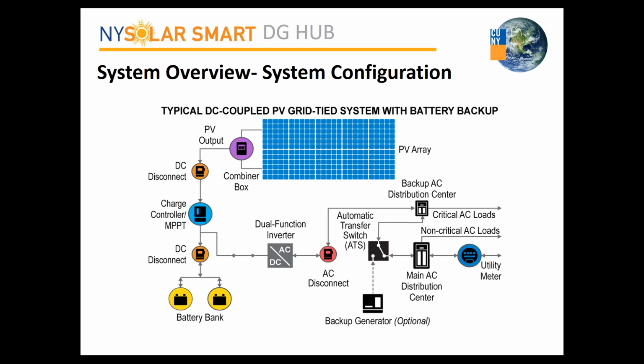We can look at how the DC coupled system integrates a battery system into your existing array. If you have a PV array in a DC coupled system, you would have to remove the grid-tied inverter and tie everything to the DC side with the charge controller and then the battery bank. Then you would add a dual functioning inverter to tie to your critical loads, the battery and the PV, and the utility is also able to charge the batteries through that dual function inverter.